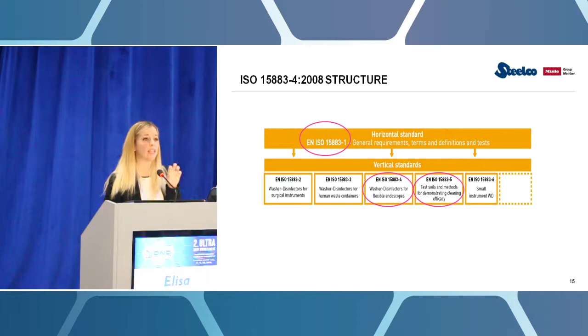Part 2 covers general washer-disinfectors for surgical instruments. Part 3 is for flushers. Part 4 is dedicated to endoscope reprocessing, and Part 5 gives indications of the tests that a manufacturer needs to perform and carry out when validating machines.